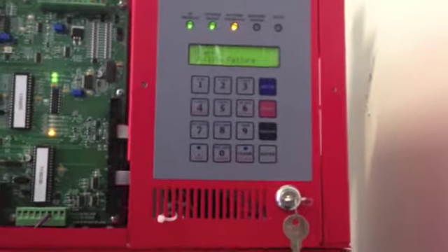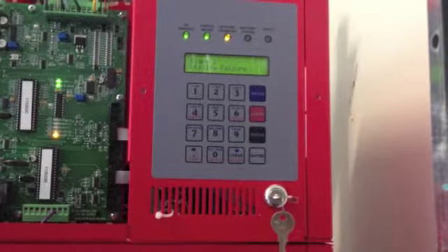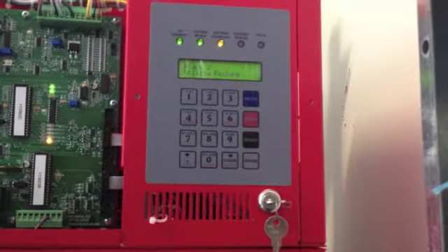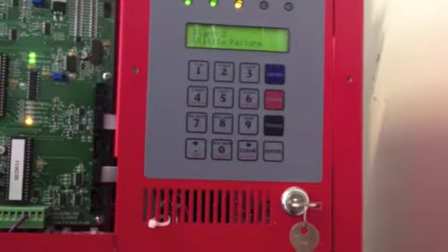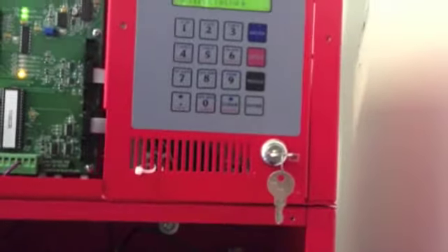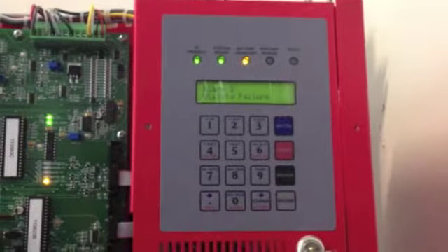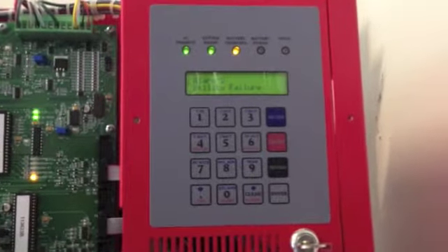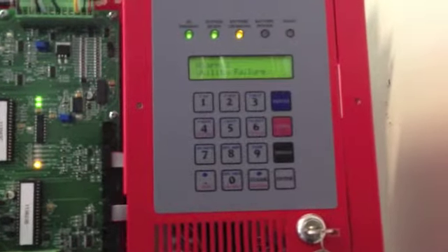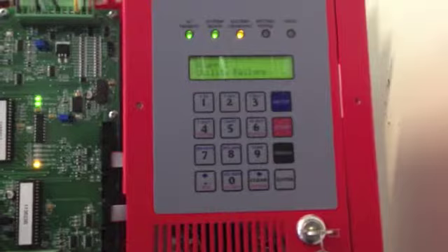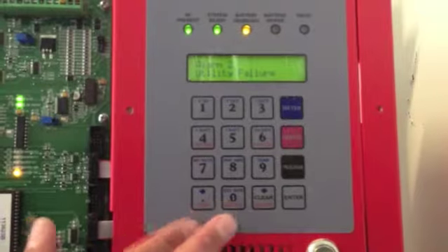There's a lot to go over in that area as far as what alarms you can have. So if you have an alarm condition, especially while it's under warranty, I just recommend you call your local service center or the manufacturer. Pose the question to them and then go from there. Again, the user's guide has a small troubleshooting chart in the rear. So if you're having an issue, you can reference that chart and see if it helps you. But they're pretty common sense, you know. Charger failure, inverter fault, output fault, overload, low VAC. So a lot of them are self-explanatory, but take them as they come, because we could do an hour just on that. So that's everything for logs.